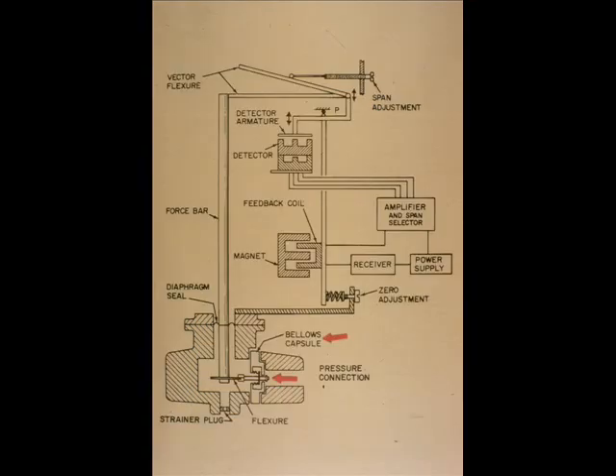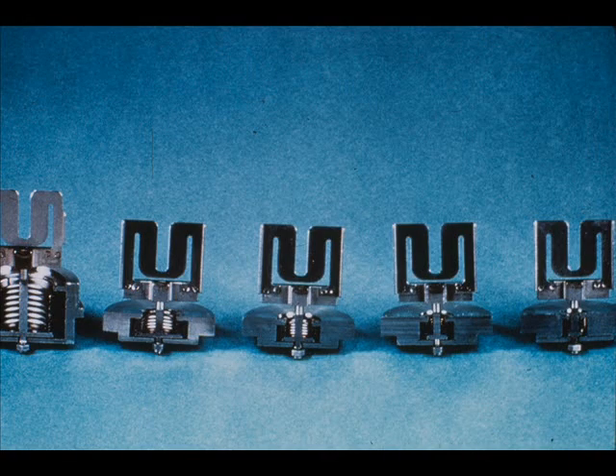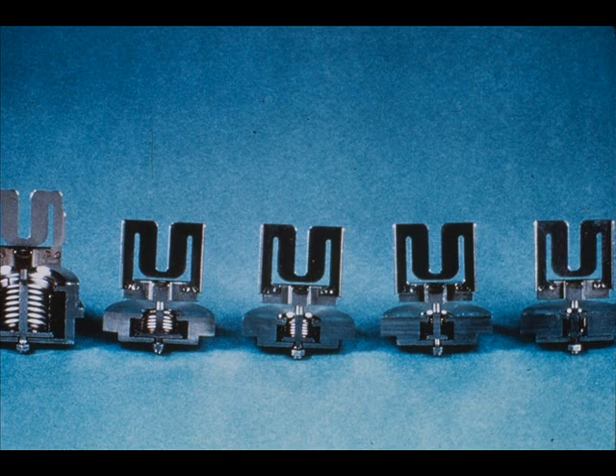The pressure being measured enters through the pressure connection and is applied to the capsule. The capsule is connected to the bottom of the force bar with the flexure. The flexures are shown attached to the capsule.